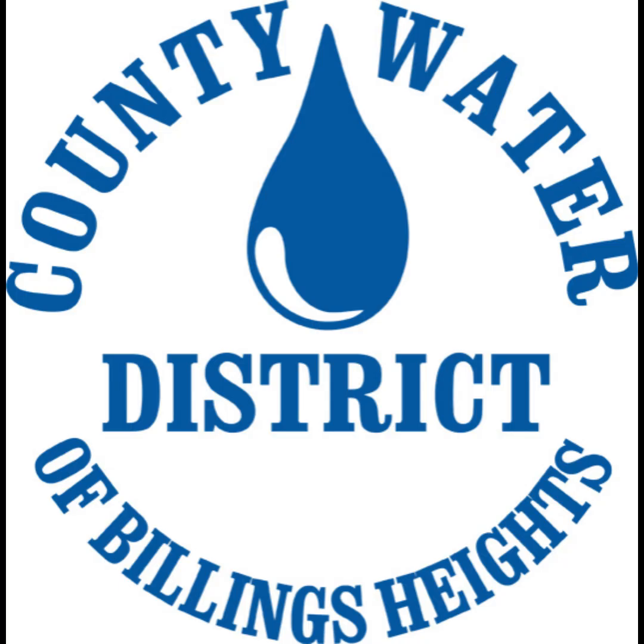And all those 6 inches too, you still gotta fight all the head pressure issues in the existing pipes to get down to the southwest corner where all the elevated areas are. So really you're fighting physics to get the water there. The further west you go, the less restrictive the southern flow would be.